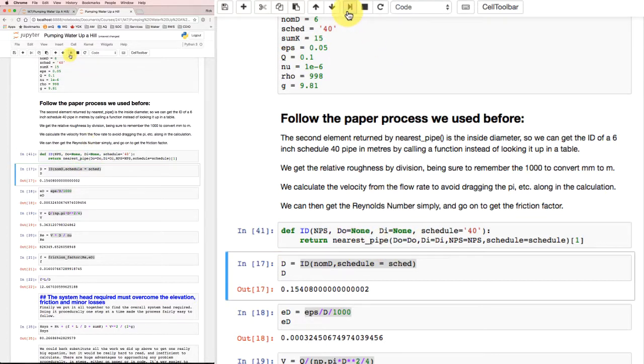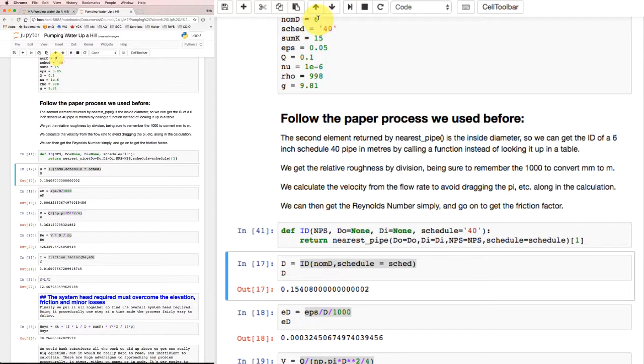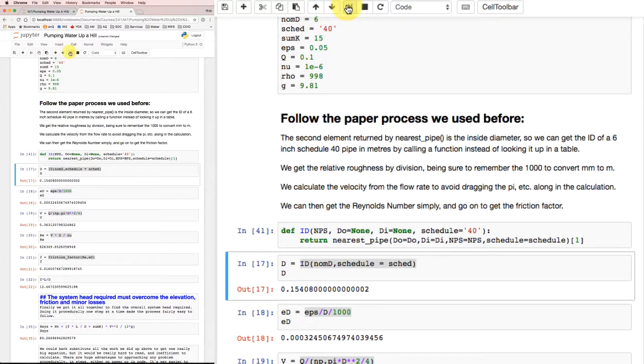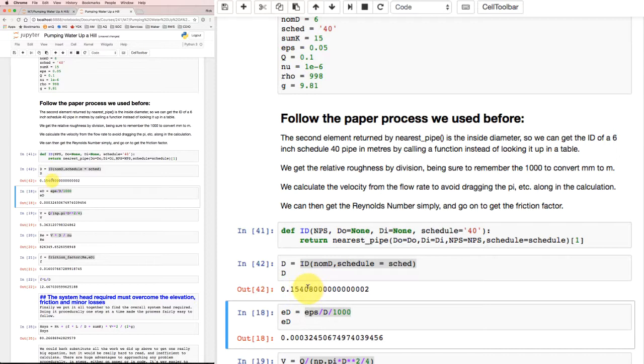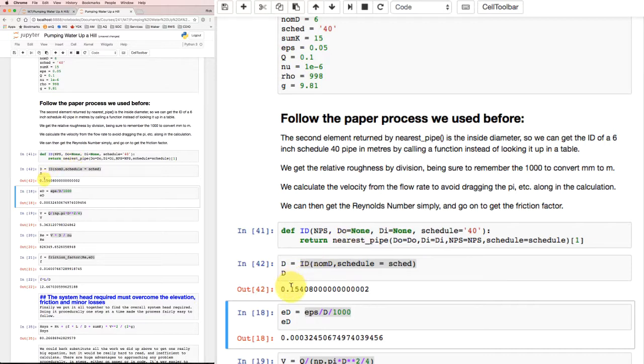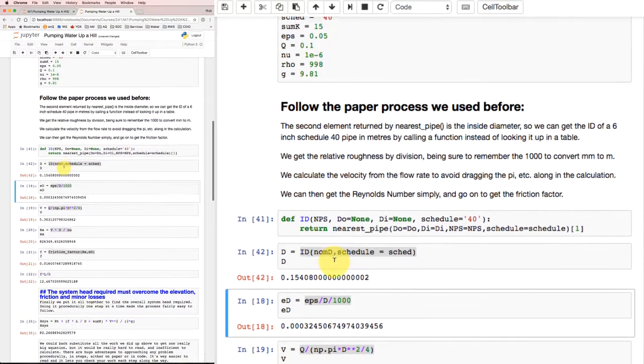Let's try this out. I'm going to define that function. Now I'm going to set d equal to the id of our nominal diameter 6 with a schedule of '40' and see what comes out. When I run it, I get 0.15408, which is really 0.1541 to 4 decimal places. That's what I got on paper before when I looked up the size of a Schedule 40 pipe - it was 154.1 millimeters. So that's good, that's working.